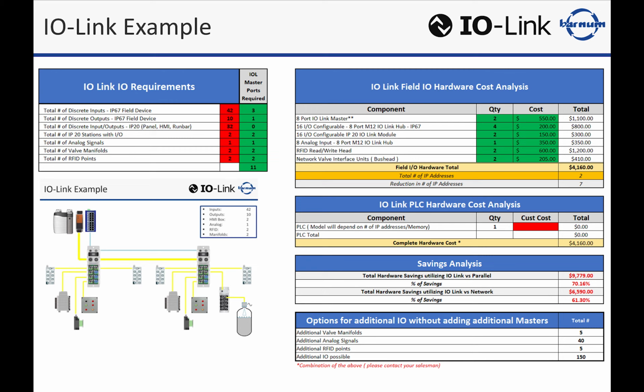That's that yellow tool cord that goes from your IO-Link master to, say, an IO hub or to a laser sensor that's IO-Link compatible, for instance. So 20 meters or 60 feet roughly if you did the conversion. And that can be an unshielded standard prox cord. The only time we really recommend using a shielded prox cord is with use of RFID read write heads. That's right. Due to noise.